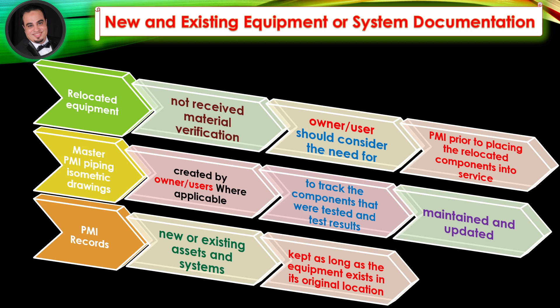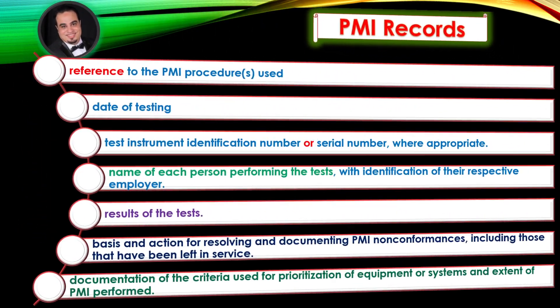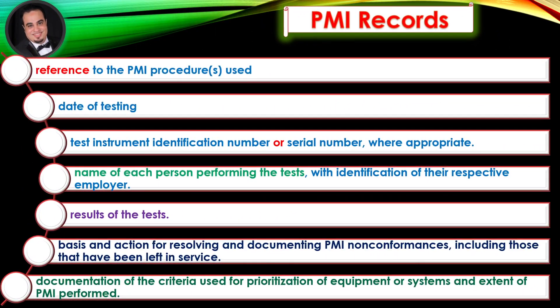PMI records for new or existing assets and systems should be kept as long as the equipment exists in its original location. Typical PMI records should contain the following: reference to the PMI procedures used, date of testing, test instrument identification number or serial number where appropriate, and the name of each person performing the tests with identification of their respective employer.